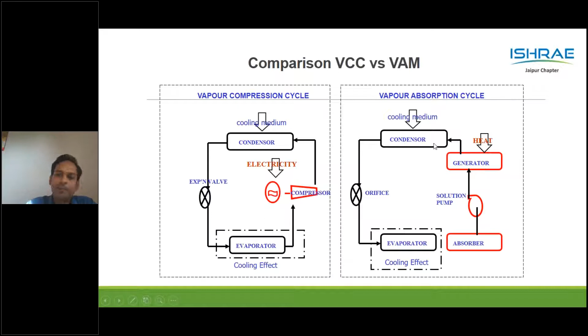The generator is the part where we take in heat. Further, I will tabulate the differences between the compression cycle versus absorption systems, in terms of the type of energy used. Vapor compression systems, like our window AC, run on electricity. Vapor absorption machines do not run on electricity, they run on heat sources, which have to be supplied in higher quantity, whereas electricity is a high grade energy required in very low quantity in vapor compression cycles.